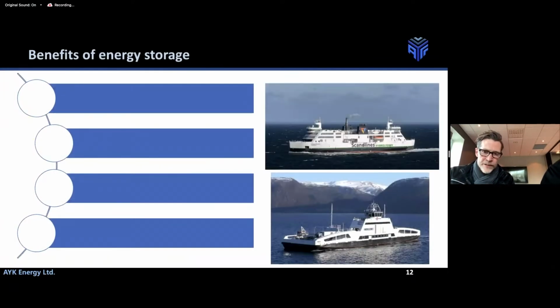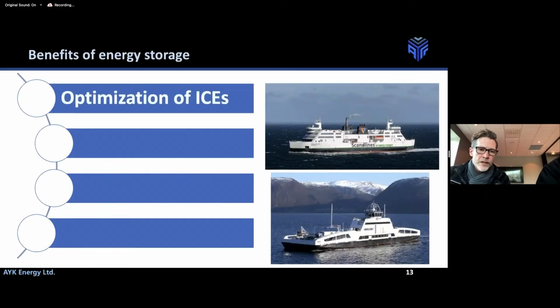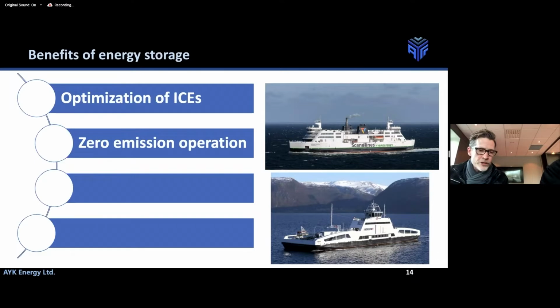Quickly going over the benefits, which I think you're all familiar with. One, and this is actually one of my favorites, is optimization of internal combustion engines. I came from that side of the world, so I feel more of an attachment with that. It's in the sense that you allow a generator to work in its more optimal range. In any application, you're going to produce so many kilowatt hours, and it's better to produce those kilowatts in a lower specific fuel consumption part of the diesel engine's range—like 40 to 80%, as opposed to 0 to 30%. So you try to avoid that low load, inefficient range of a fuel burner. The other is zero emission operation, which we're all familiar with.